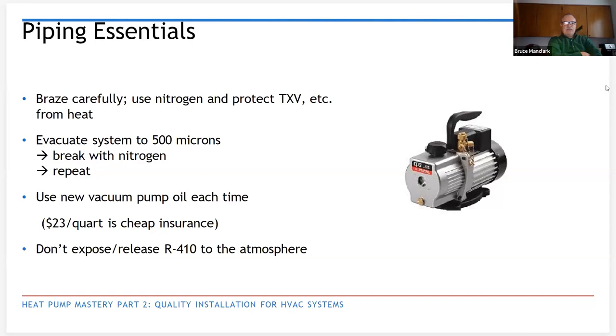Matt, why is it important to do that evacuation? It's pulling all of the non-condensables out of the lines. So everything's been connected, everything's been pressure tested. You then start vacuuming. You're pulling all of the non-condensables, all of the moisture, everything out of those lines. The only thing that's going to be in those lines when you're all done is refrigerant. If any moisture is in there, that mixes with the compressor oil, causes acid, and can damage the system long term. If you have non-condensables in there, as the refrigerant boils and condenses, when those non-condensables mix in there, you lose performance, and over time it can also cause damage to the system.